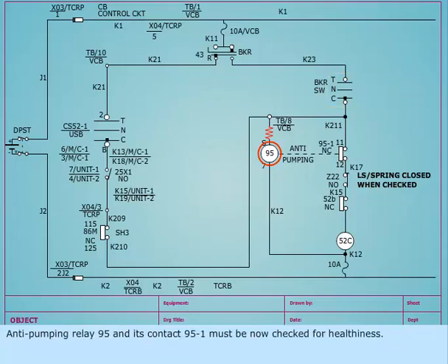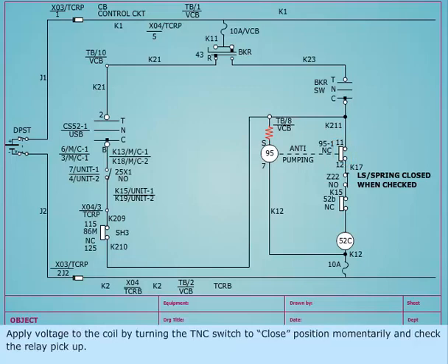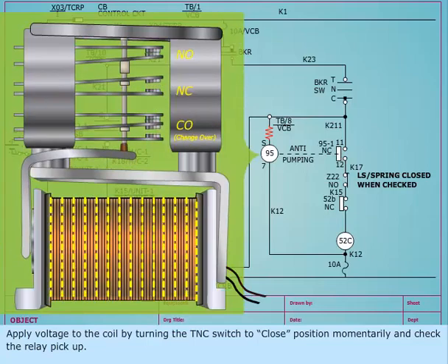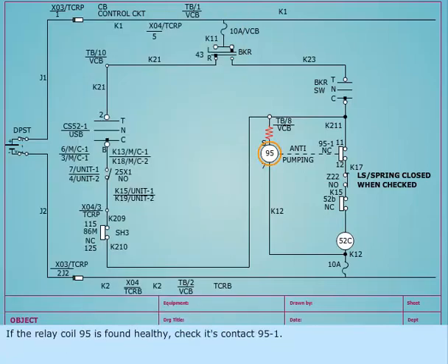Anti-pumping relay 95 and its contact 95-1 must now be checked for healthiness. Apply voltage to the coil by turning the TNC switch to close position momentarily and check the relay pickup. If the relay coil 95 is found healthy, check its contact 95-1.